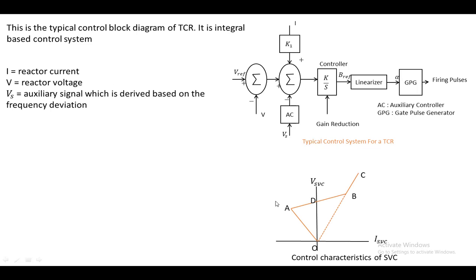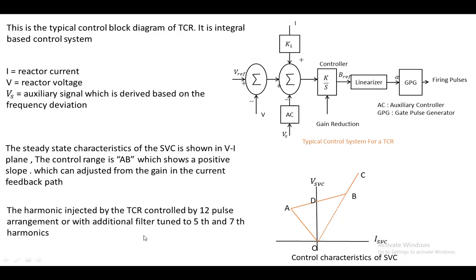The SVC characteristics on a V-I plane show the control region as line AB with a positive slope, which can be controlled by changing the gain in the current loop. The harmonics injected by the TCR can be reduced using a 12-pulse arrangement, or additional AC filters to filter out the 5th and 7th harmonics generated by the TCR.